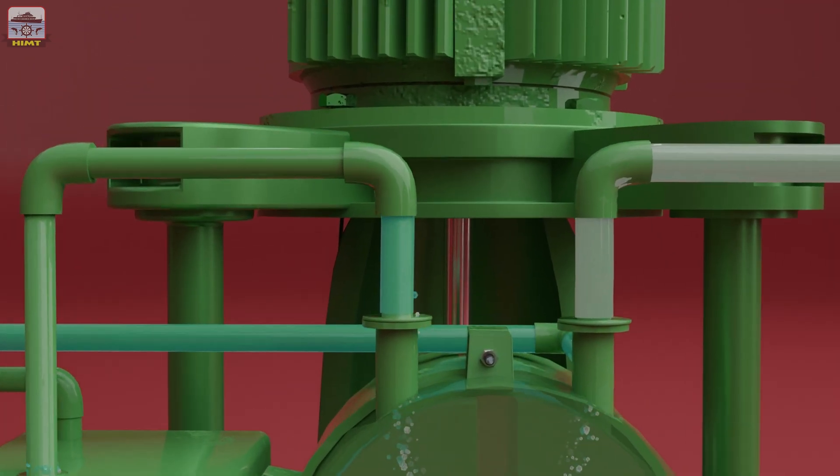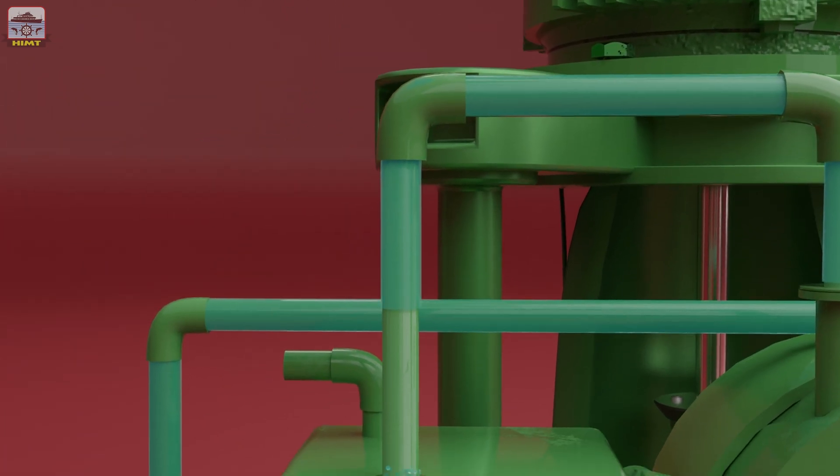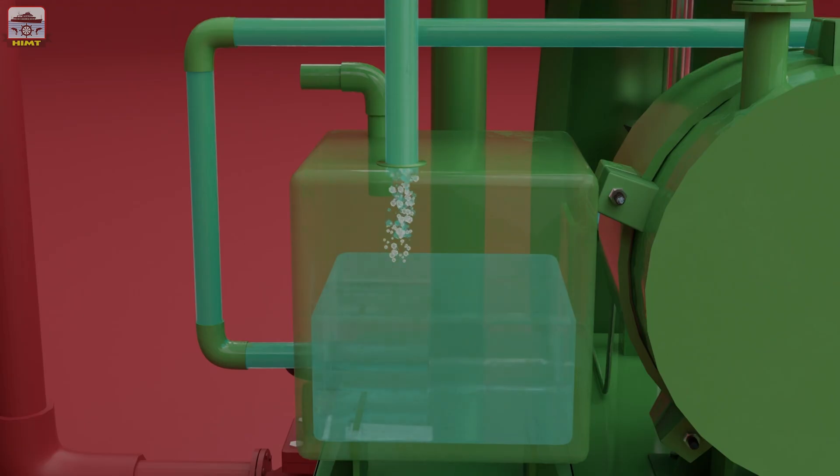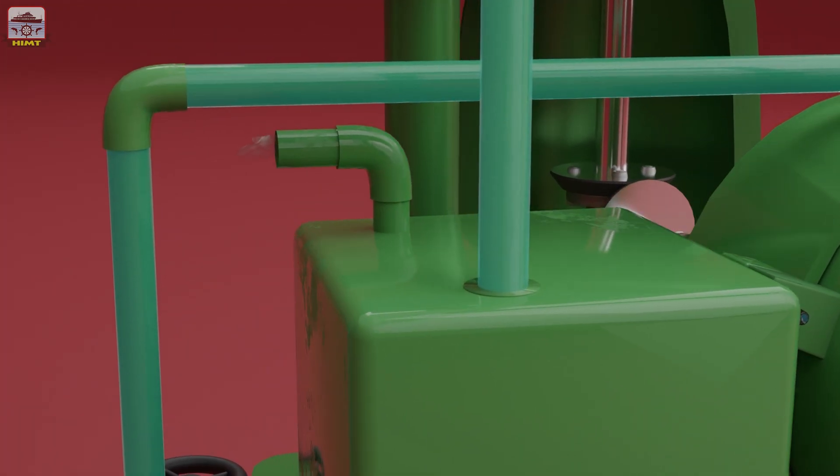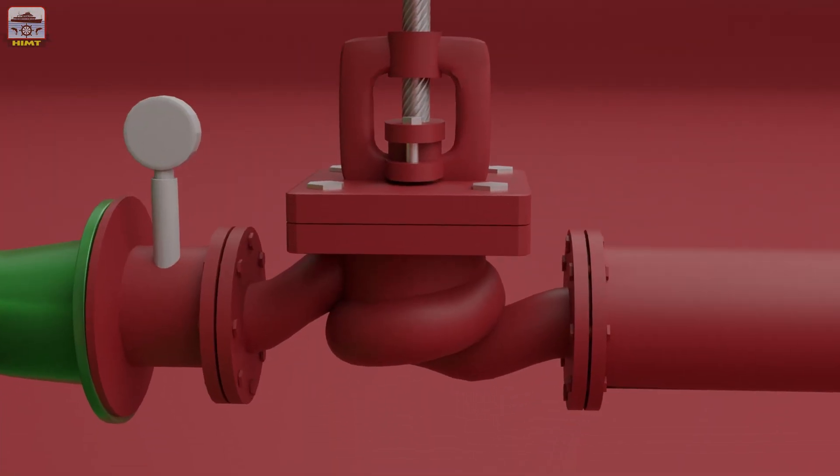This causes continuous suction of air from the main pump and discharge of air into the sealing water tank. As the air is continuously removed from the main pump casing, vacuum is created inside the main pump casing.